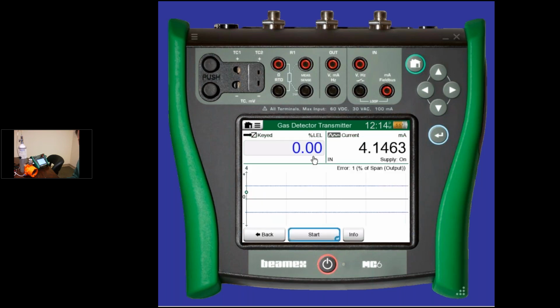And so now here we are sitting at, and this is kind of interesting, it's come in a little bit here. Maybe having that cap on there was messing it up. So the way this guy works, as Roy said, we use a magnet. So you can see there's this little device here. But Crowcon designed this so that you can move the transmitter without taking off the cover and exposing the electronics to a potentially harmful or intrinsic rated area. So you don't have to come out with a hot work permit.